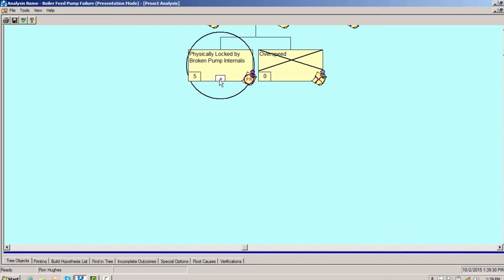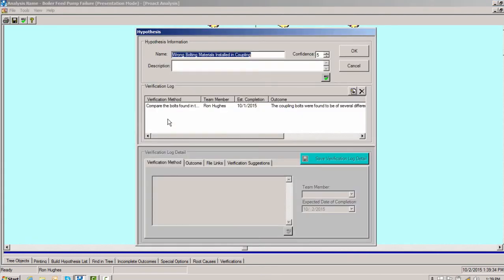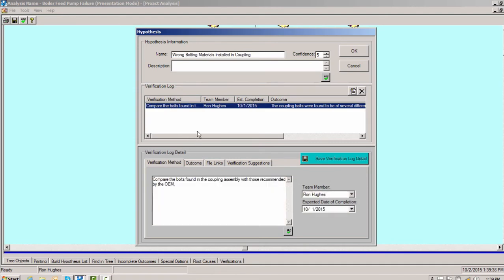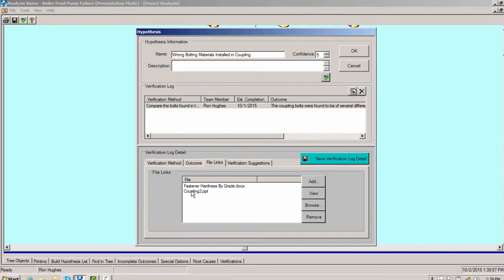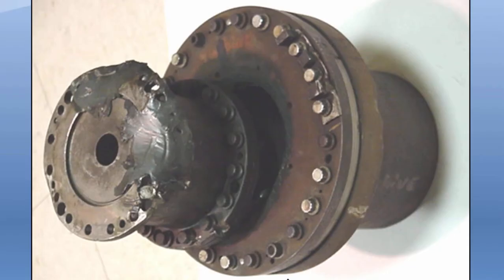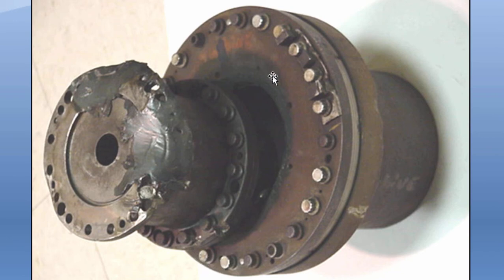So it's definitely a coupling bolt that caused this pump to seize up — we actually find it. How can that be? Wrong bolting materials were installed. When we look at what bolting materials were installed and compare with OEM recommendations and recommendations from the ASME code, we find that the OEM recommends all bolts be grade eight and that the pump coupling be perfectly balanced. If you look here, Allen heads are all grade eight — six radial dashes, that's a grade eight. We actually have all different types and grades of bolts: variations between grade one, three, five, and eight. If this was a perfectly balanced coupling, why do you need balancing weights? So we've got a problem with our coupling bolting.